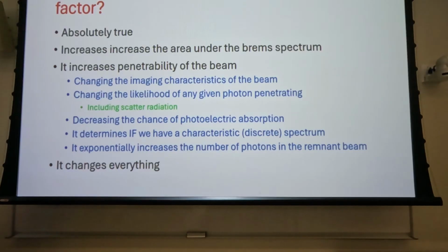A factor of either one of them individually. It's a factor of 2, right? So it's a direct relationship. Now, how much of a change in kVp do you need in order to affect an equivalent output from your X-ray tube? Well, unless you've been through the PowerPoints, you don't really know. And if you didn't listen to the thing, which again I did the math wrong, you still don't know, right? But if you increase your kVp by 15%, you get about a 70% increase in output from the X-ray tube. Not only that, but that 15% in kVp equates to a doubling at the image receptor. So it's even more significant at the image receptor than what it is coming out of the X-ray tube.